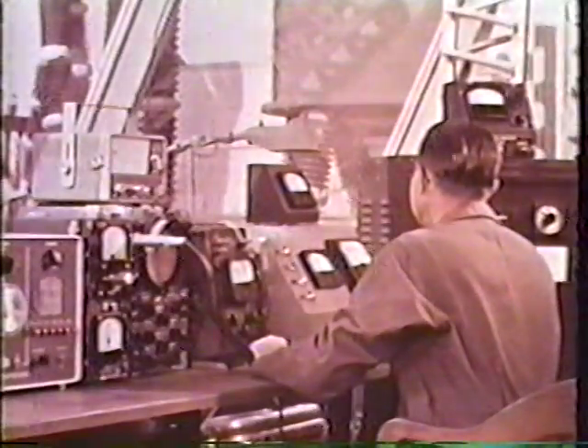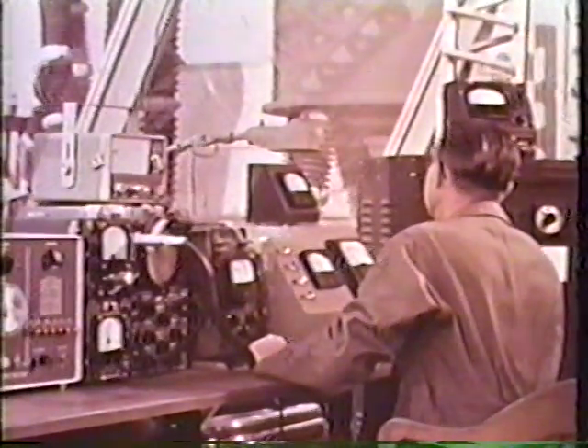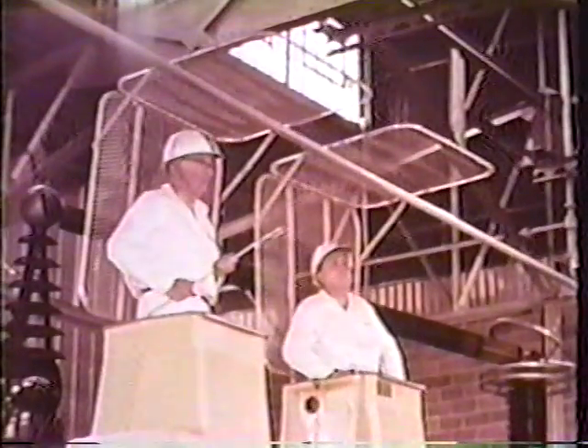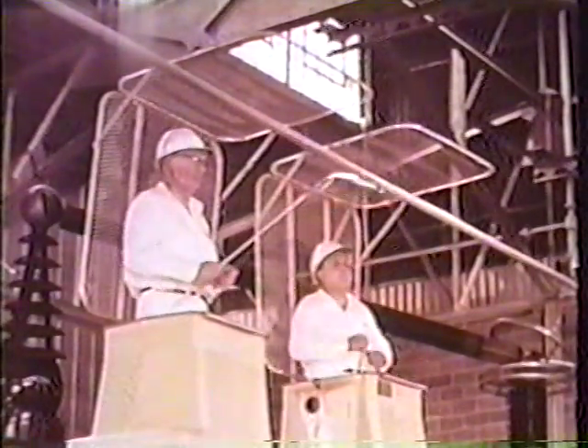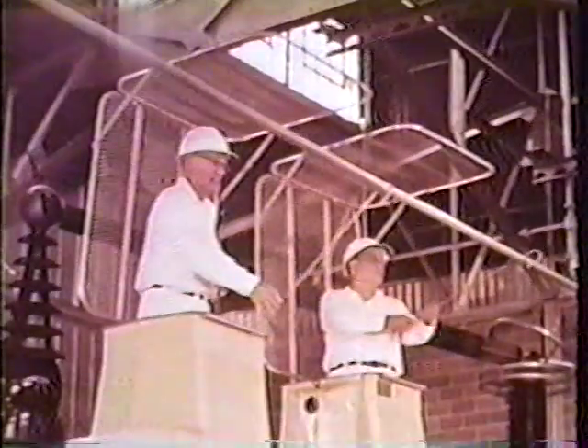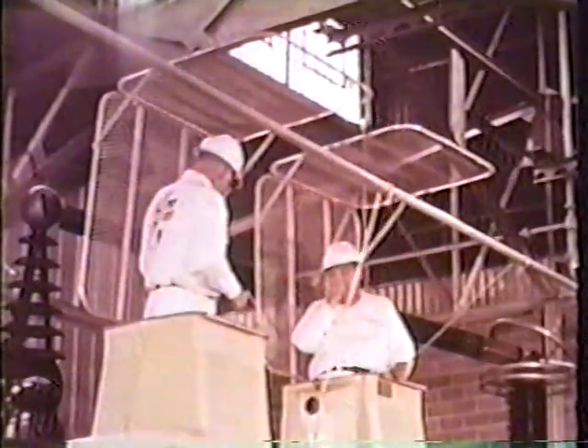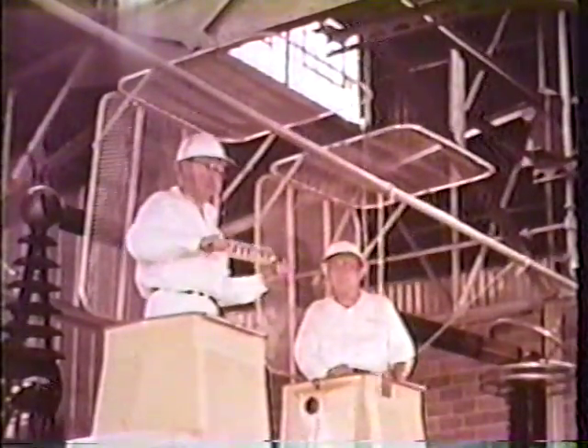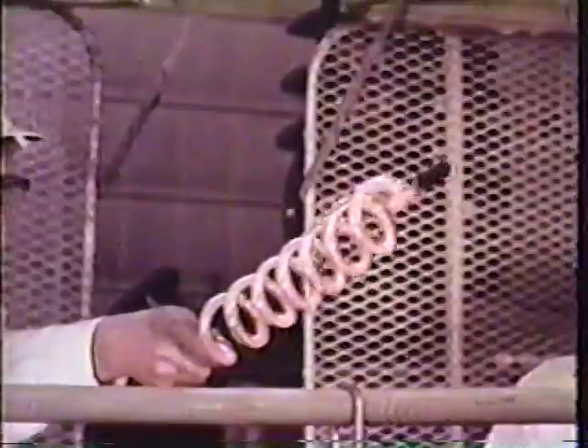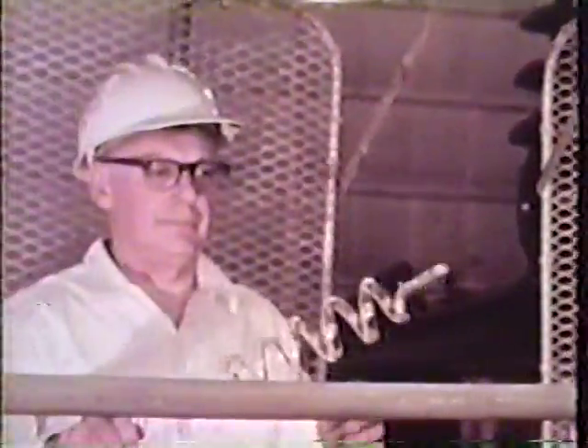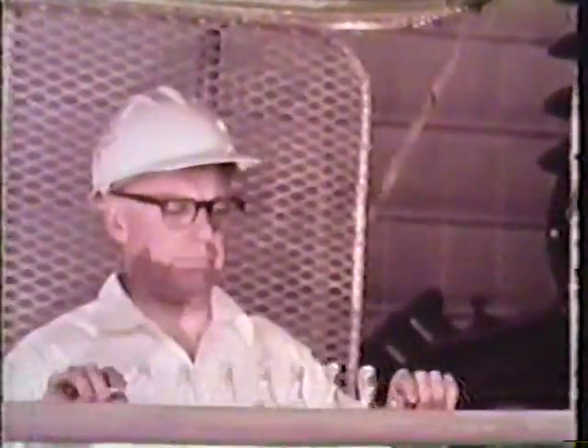When the line is energized at 500 kV, the line-to-ground voltage of an 866 kV system, charging current sparks jump across the 32-inch gap between conductor and shielding. Attachment of bonding leads to the conductor brings men and shielding to conductor potential. A neon tube clearly demonstrates the effectiveness of the shielding. The tube lights up in the electrostatic field outside the shielding, but no field exists within the shielded work area. If a lineman puts his hand outside the shielded area, he would feel a harmless tingling sensation due to a very small charging current at his fingertips.